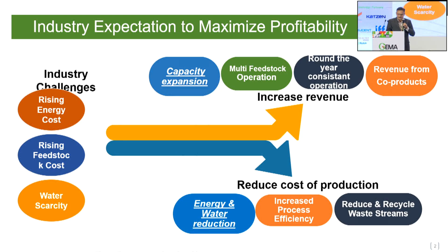The starting point of reducing consumption of energy is to have accurate measurement. In a total ethanol complex, it is very important to measure energy production and consumption, starting from the boiler — how much steam is going into the turbine, at what pressure, how much is the internal consumption of the boiler, how much steam is going back to the deaerator and at what pressure, and finally how much steam is going to the process plant.